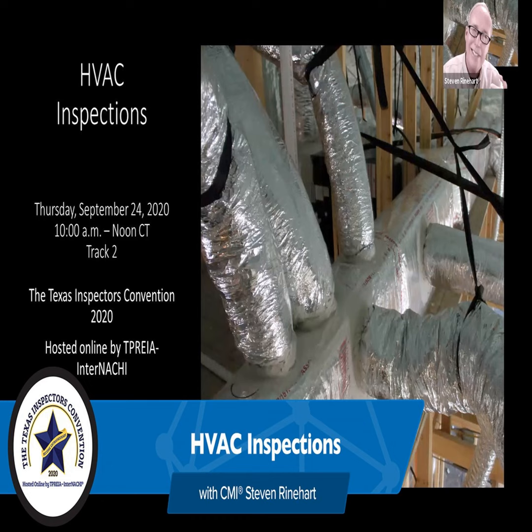Condensing furnaces. I have a condensing furnace, really nice. Don't see a lot of them, but the first time you go up in the attic and you see an air handler and you see PVC, Schedule 40 coming out of it, you're like, what the heck? That's a condensing furnace. Mine is 97% efficient. That means very little heat is lost up the flue, so they can make it with plastic, PVC.